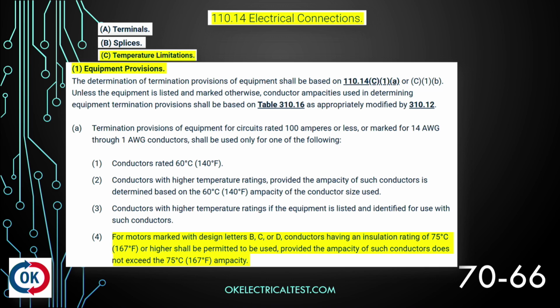Now, if I was looking for a test question and I couldn't find it, what I don't want to do is read through all of this stuff if I'm not looking for electrical connections, because everything under 110.14 is talking about electrical connections. So when we get to letter A, this is terminals for electrical connections. Letter B is splices for electrical connections. Letter C is temperature limitations for electrical connections. Now let's say what I was looking for was high leg marking. Well, then I can skip over everything that is under 110.14 and jump to 110.15. 110.15 is high leg marking. Okay, that's what I want to read.